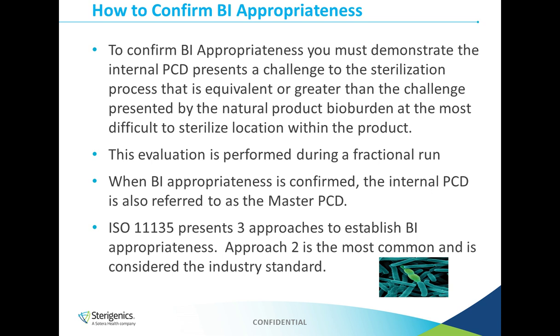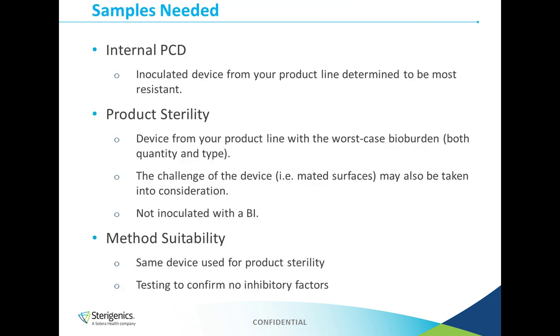During this webinar, we're just going to touch upon approach number 2, because this is the most common and it's the industry standard. Now, for this fractional run, the samples that you're going to need are your internal PCD, which we talked about, that inoculated device that you determined to be worst case. You're also going to include your product sterility samples.